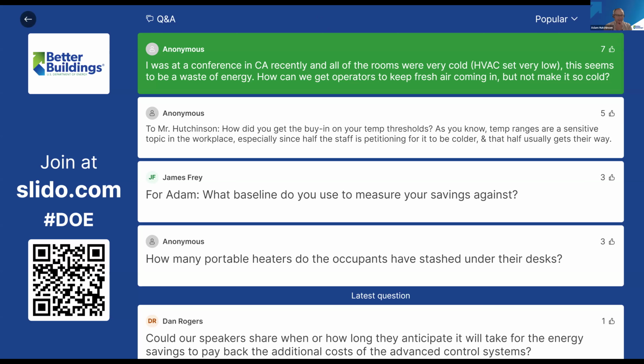I should reiterate that those setback temperatures and even our set points, I really think it's because of the radiant heating and cooling. It makes such a difference in how a space feels, and it's not forced air. To answer this question, we actually use a dedicated outdoor air system, the DOAS. It took me a while to figure out how we were getting savings from that, but you can even use them with forced air systems, bringing in outdoor air without mixing it with the return air, to help meet your CO2 levels while also reducing HVAC costs.